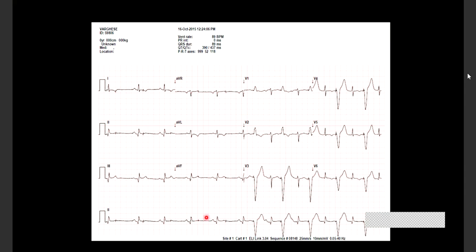That is unfortunate, because the pacemaker is supposed to see this intrinsic activity and stop pacing. The reason it is not doing that is because it's not sensing this. It's undersensing this intrinsic activity, and that's why it's pacing. So obviously, this is an undersensing problem. This could be that the pacemaker has been programmed to asynchronous mode, or this one, this is unlikely to be a magnet.